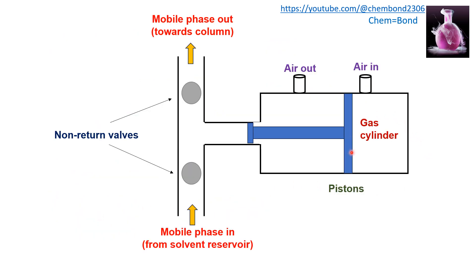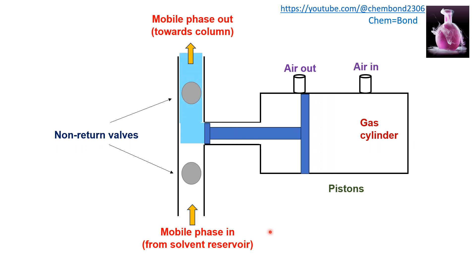For the working of the pneumatic pump: a gas cylinder is used with two valves — one for air in and one for air out. Two pistons are used — one large and one small. The mobile phase enters from the solvent reservoir through one part of the tube, and the other part connects to the column. There are two strokes: forward and reverse. In the reverse stroke, mobile phase enters from the solvent reservoir; in the forward stroke, the gas pressure moves the piston to push the mobile phase towards the column.